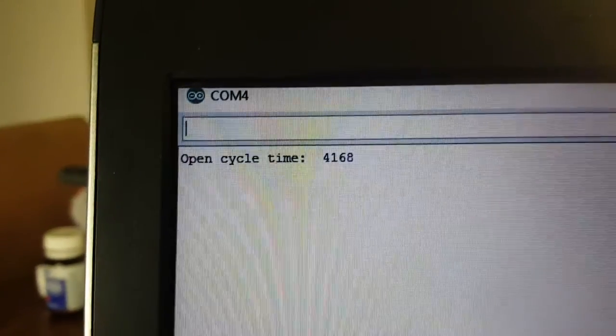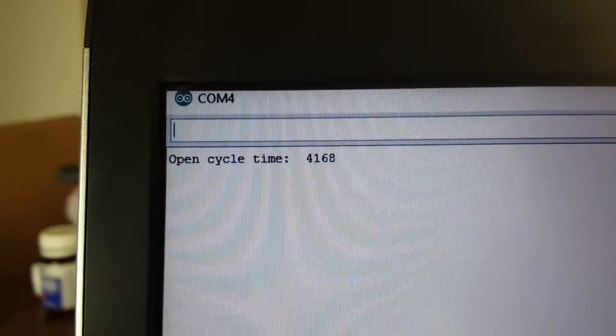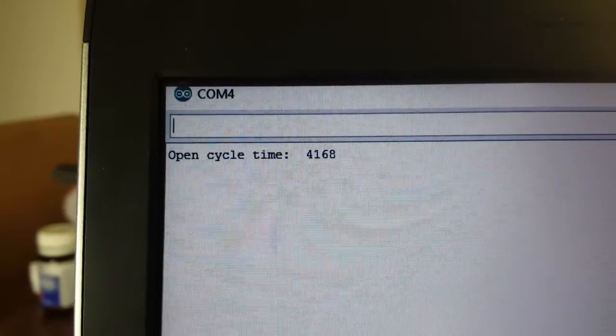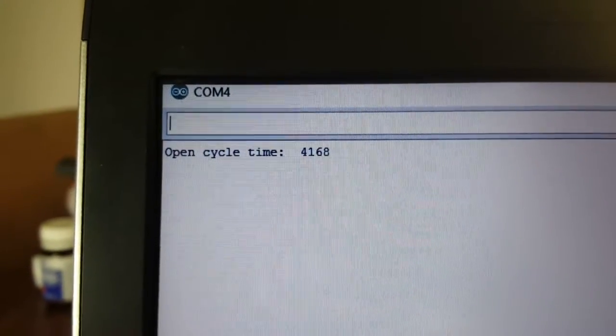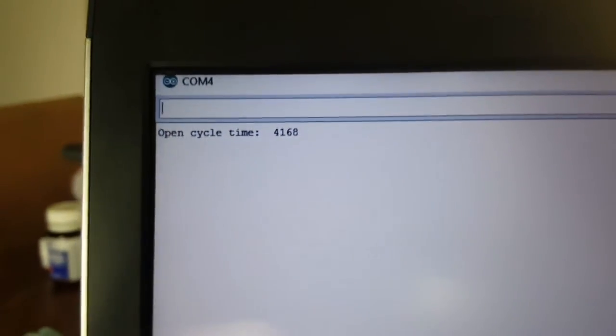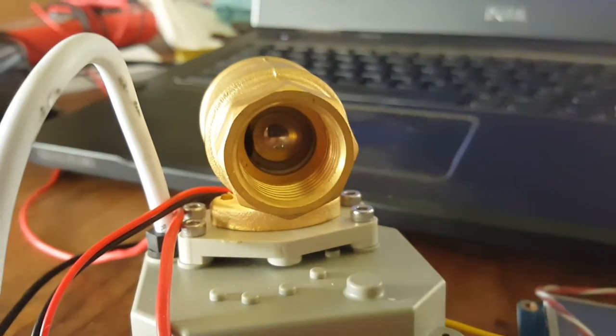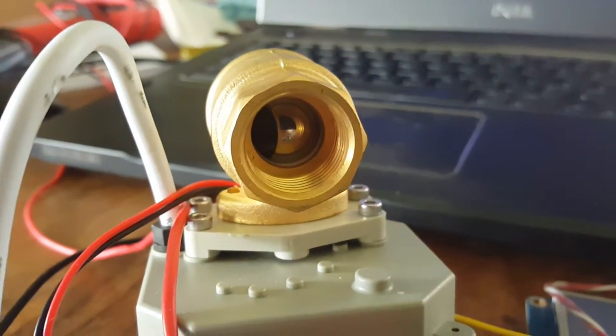So the machine is going through that process at the moment and has found the open cycle time would be 4168 milliseconds, and it's now performing the search for the closing time.